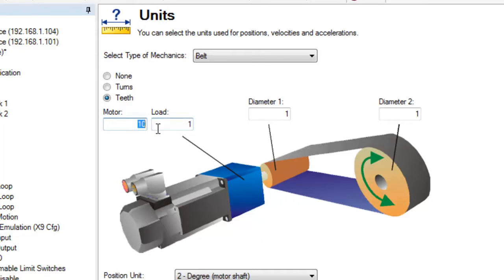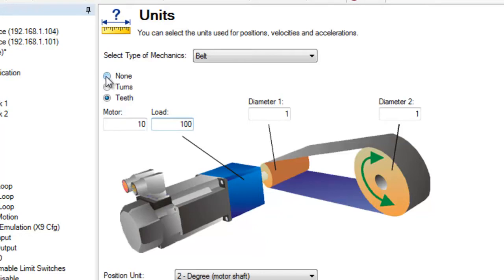With a pulley and belt ratio, set the number of teeth on the motor pinion and the number of teeth on the load pinion. Still using a 10 to 1 ratio, we could enter 10 for the motor and for the load 100, or any combination that would give us 10 to 1.